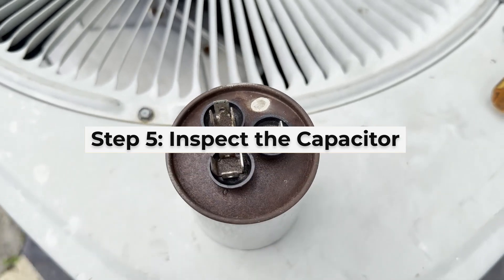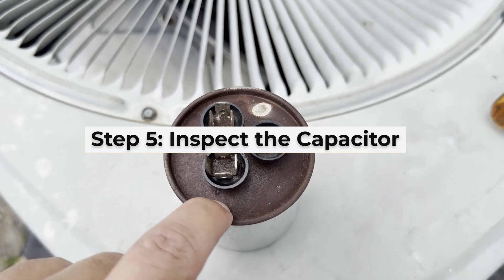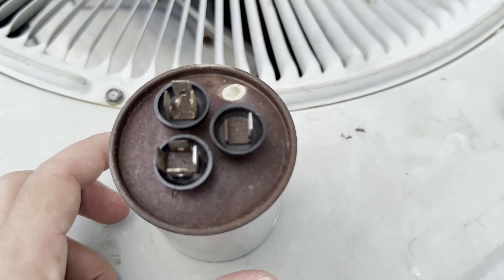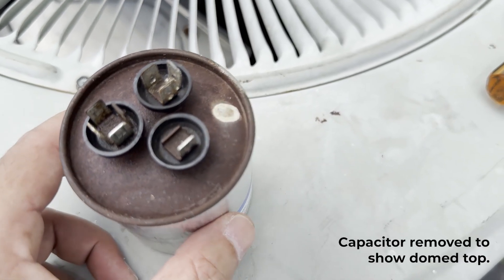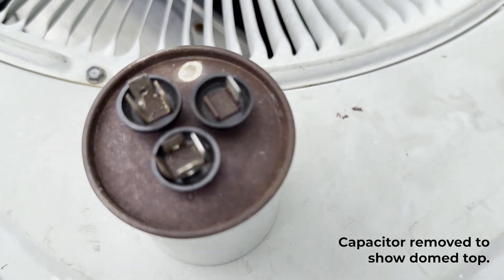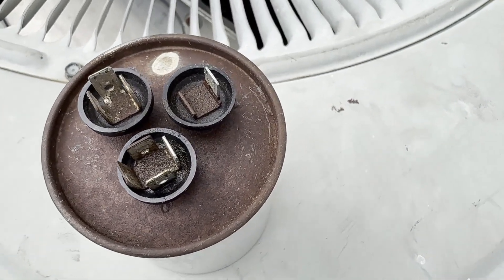Step 5: Inspect the capacitor. Look at the top. If it's bulging or mushroom shaped, it's bad. If it's leaking fluid, it's also bad. Even if it looks fine, testing is the only way to be sure. In our case, you can see it's domed and bubbled up. Still, we're going to test it to confirm.